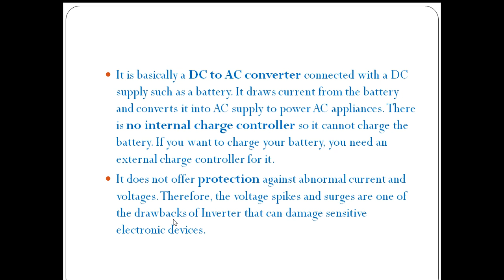It does not offer protection against abnormal currents and voltages. Therefore, voltage spikes and surges, which are drawbacks of the inverter, can damage sensitive electronic devices. So these are the main comparisons between UPS and inverter. The switching speed of UPS is 2 to 5 milliseconds, and the switching speed of an inverter is around 200 to 500 milliseconds. This is the main differentiation between UPS and inverter.